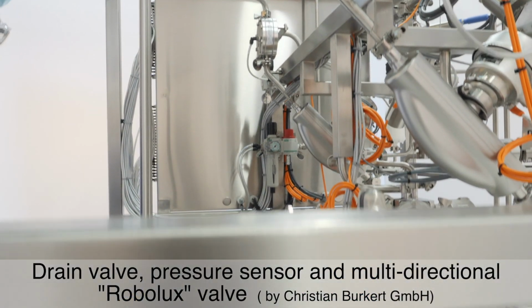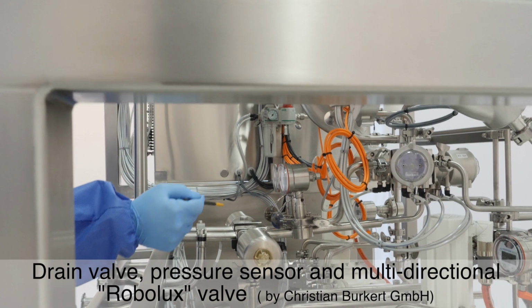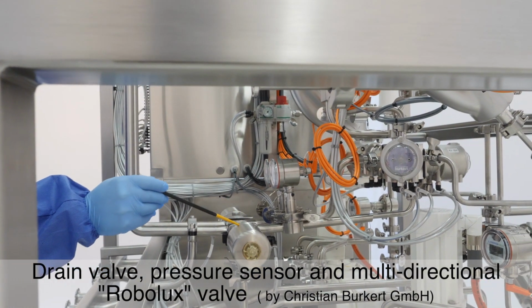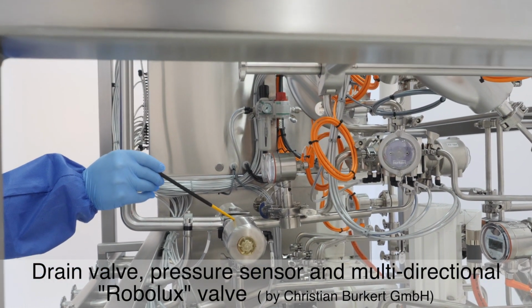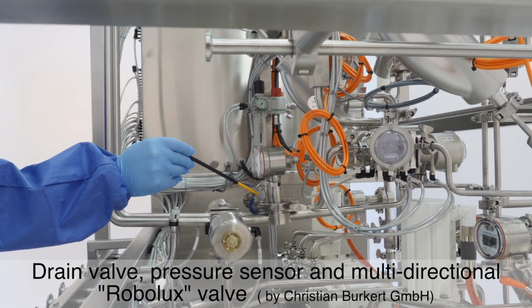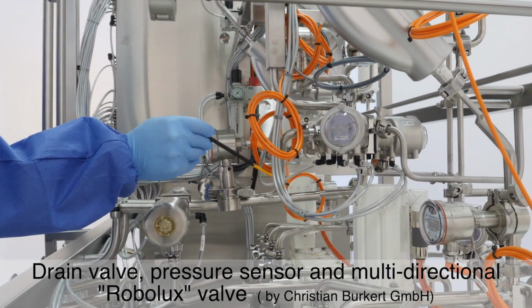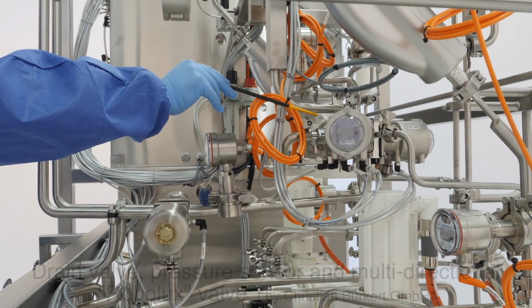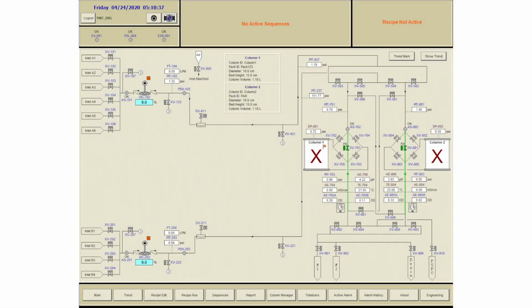Towards the end of this section of the flow path, behind the pumps, there's another drain valve, enabling quick buffer changeovers, and pressure sensors prior to the first Robolux valve. Now we have completed the first part of our tour. Let's take another look at our HMI roadmap.